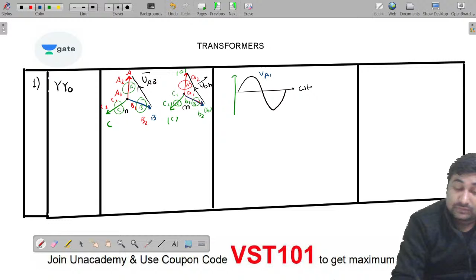We have the transformer here, and after conducting a polarity test in case of three different transformers, we know about A2, A1. Capital letters represent the HV side while small letters represent the LV side. The phasor diagram suggests how to connect the three phases in order to get a star-star zero connection.